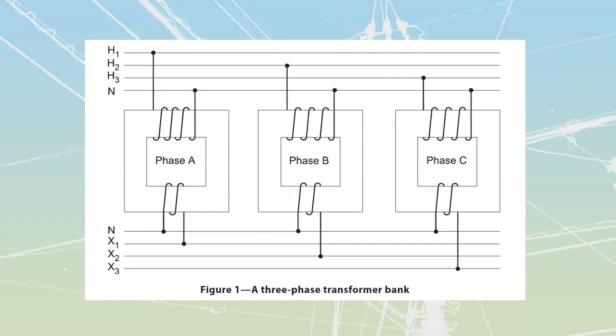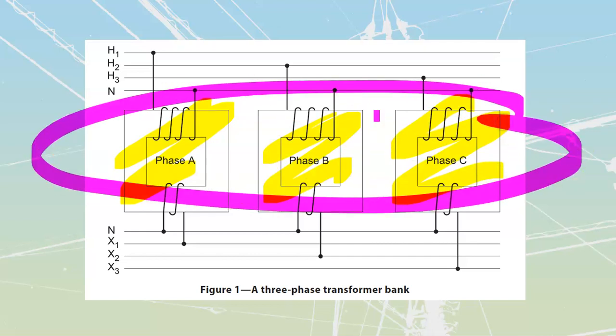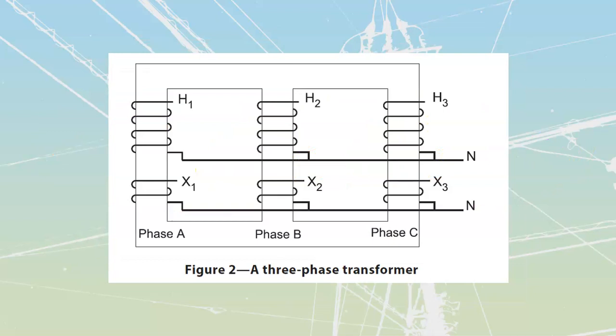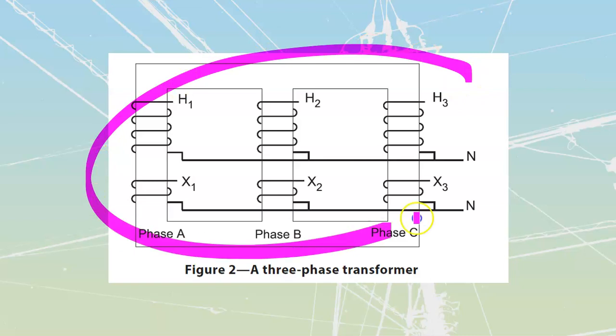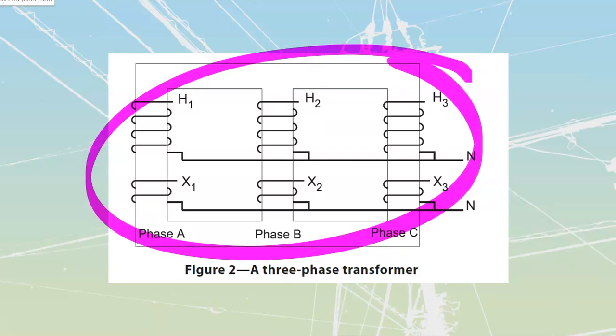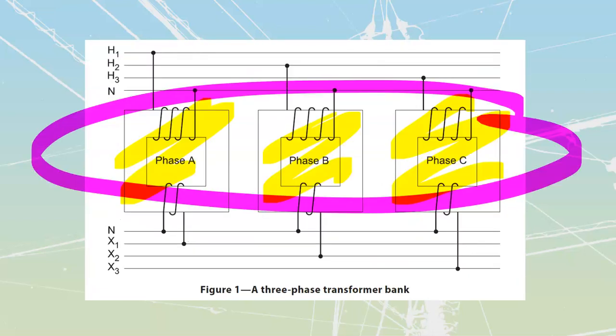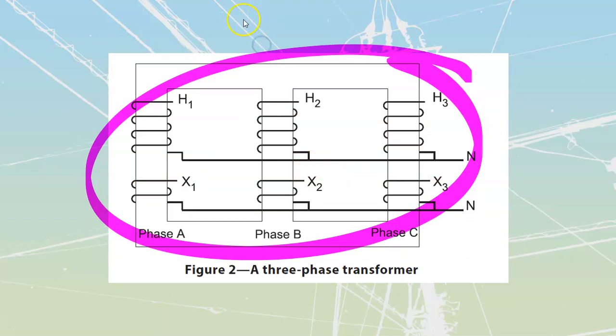Three-phase transformers are constructed one of two ways. Either we can take three individual transformers, like what we have over here, and connect them together as a bank—we'd call this entire setup a single transformer bank. Or alternatively, we can have three transformer legs wound off of a single core; this is what we refer to as a three-phase transformer, where we've got a common core and the high and low voltage windings are all wound around the same legs. The first setup is a transformer bank because it's made up of a bank, or collection, of three different transformers. For the other, we just call it a transformer, and we'll use the short form TX. Anytime you see me writing TX, it stands for transformer—just a shorter way to lay this out.